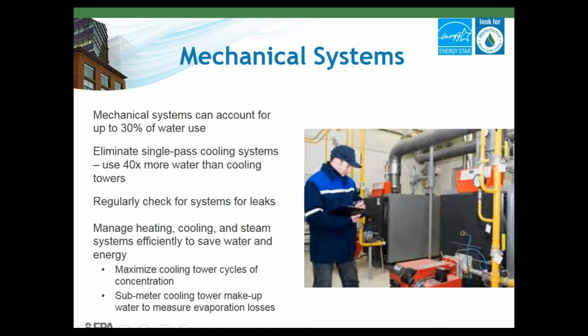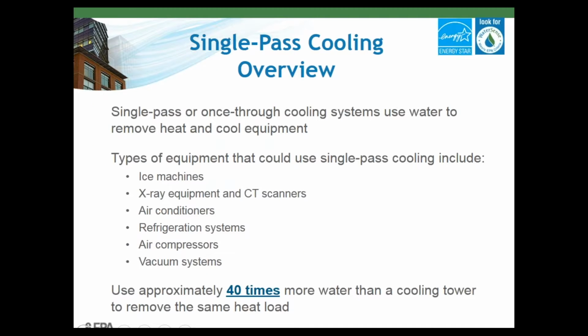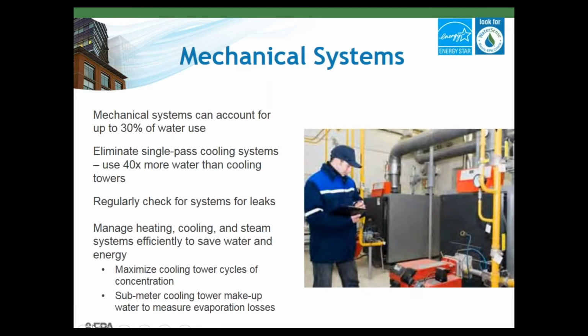Continuing a little more, the cooling towers are often the largest user of water in a facility, running between 20 to 50% of total facility water use, and they use a lot of energy to pump water through a system continuously. Some cooling towers use single pass systems, but these should be eliminated and retrofitted with a recirculating system, so we can start maintaining higher cycles of concentration throughout.